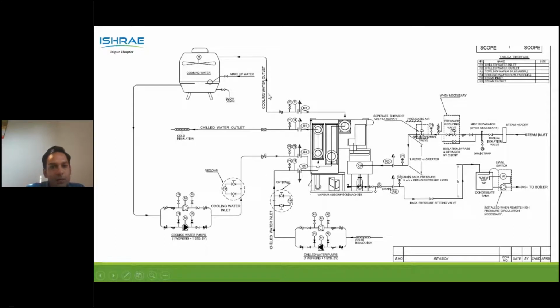The second circuit is our cooling water circuit, in which from the cooling tower suppose at 32 degree the cooling water is pumped into the VAM, and all the heat is further rejected in the cooling tower. This is the steam circuit and the condensate which is coming out. The steam inlet, you can say that this is a steam header, and here we have a pressure reducing valve if necessary to reduce the pressure of steam to the limits required by VAM. Here we can also put a desuperheating station to further reduce the temperature of the steam.